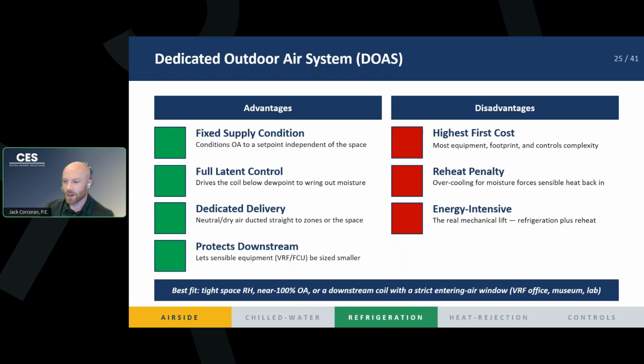So the best fit for this DOAS type of unit is when you have tight space temperature and humidities in your space, right? You need to hit that tight target. You need a DOAS unit. Or this is best for when you have a strict entering air condition, like a VRF system, right? It can't handle the high latent loads. So you handle the latent load with a DOAS system.